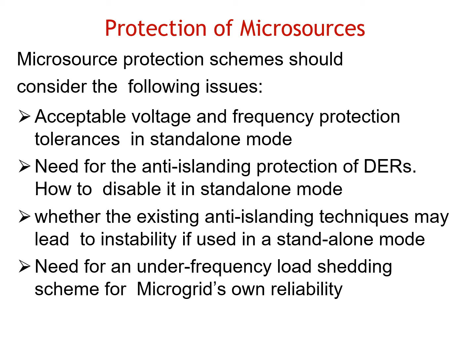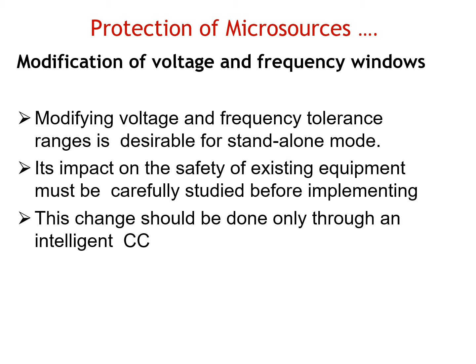microgrid. And the last one, we need to evaluate the requirements for an under frequency load shedding scheme for the microgrid and coordinate it with the same scheme of the utility. So broadening the tolerance range, that is of frequency and voltage windows, is advantageous for standalone microgrids. But before implementing the change, its effects on the safety of existing equipment must be studied carefully. And this change must be done only through the intelligent microgrid central controller.